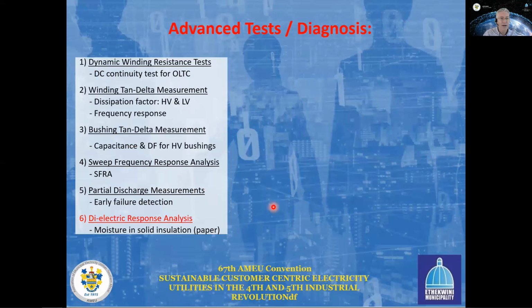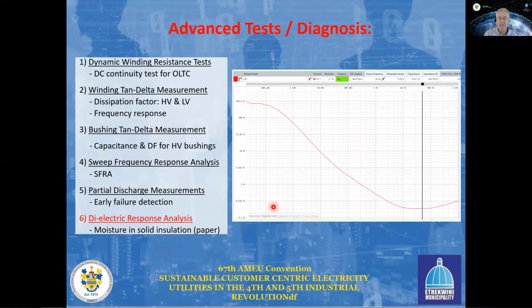And the last test to apply is a dielectric response analysis test, where we are plotting the tan delta again. So similar to the winding tan delta measurement, we were plotting the tan delta of a power transformer, but over a very wide frequency range. The value at 50 Hertz that you can see here should be very similar to the same value that we measured after 2 above, meaning 0.19% in this specific case. But in this case, we're looking at a very wide frequency range from 0.1 millihertz up to about 5 kilohertz on the top here.